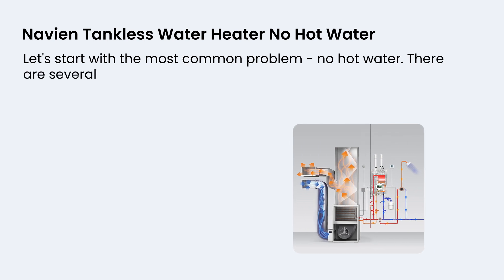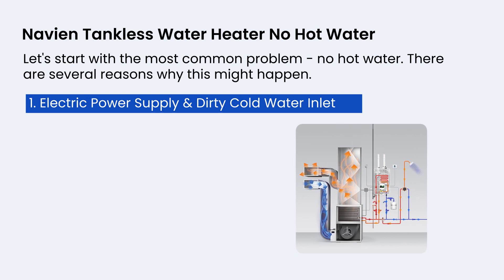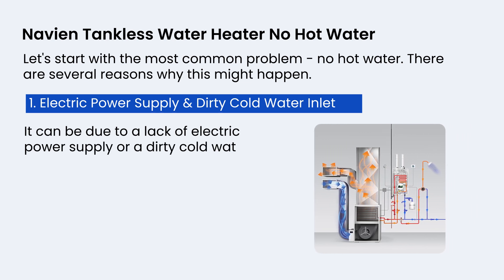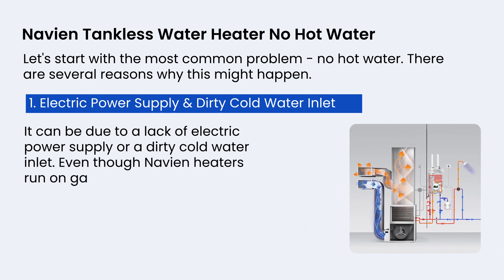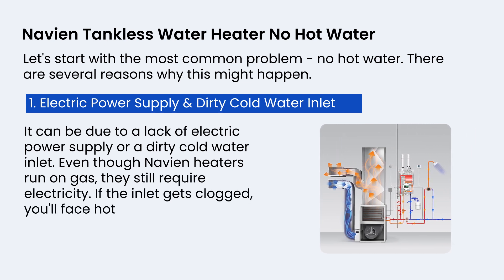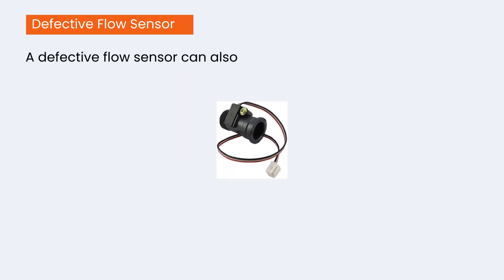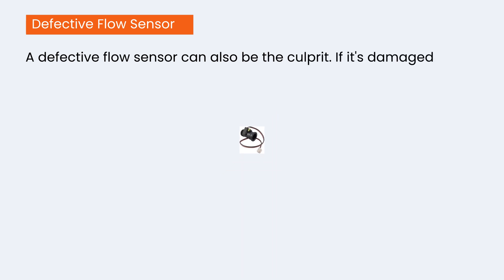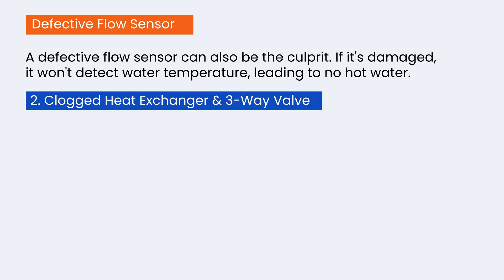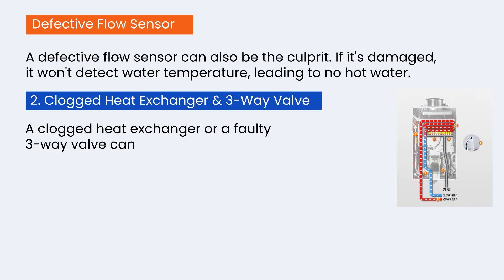Let's start with the most common problem: no hot water. There are several reasons why this might happen. First, electric power supply and dirty cold water inlet — it can be due to a lack of electric power supply or a dirty cold water inlet. Even though Navien heaters run on gas, they still require electricity. If the inlet gets clogged, you'll face hot water issues. Second, a defective flow sensor can also be the culprit — if it's damaged, it won't detect water temperature. Third, a clogged heat exchanger or a faulty three-way valve can also prevent your water heater from providing hot water.